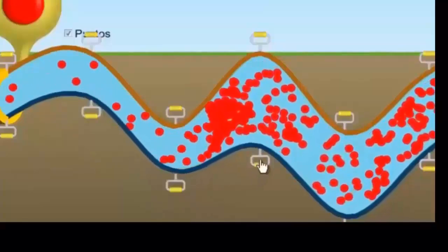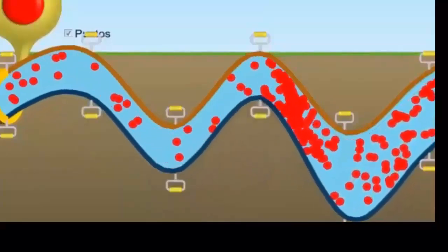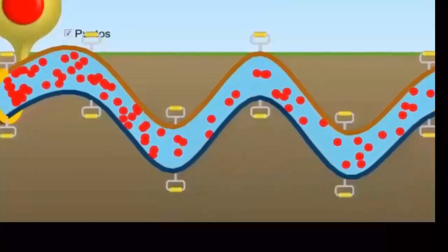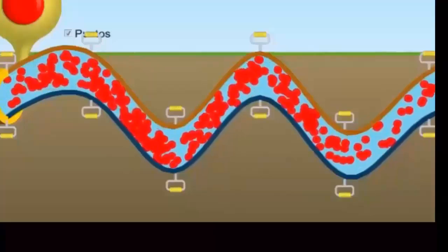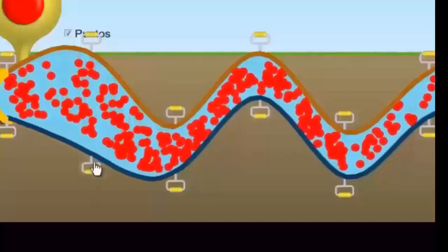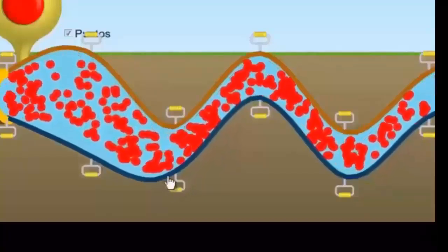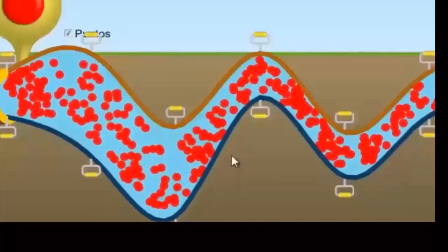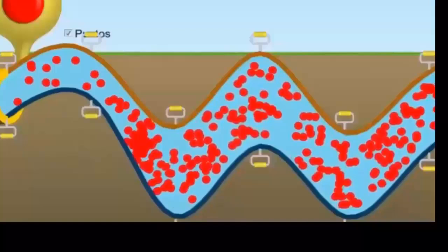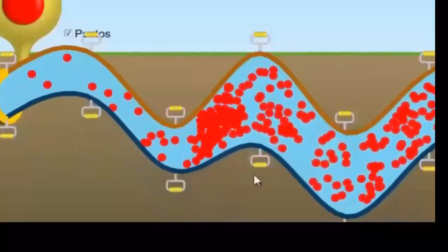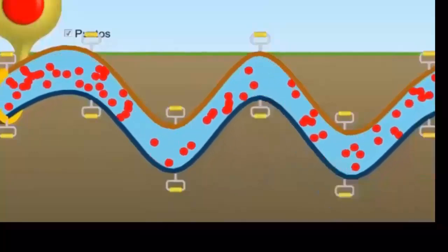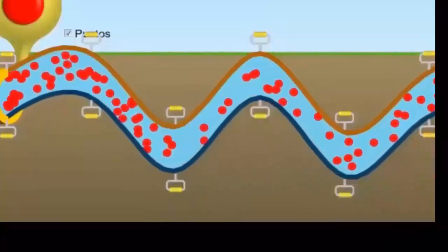E. Adjusting the capillary length is a better method for calibrating its final restriction. F. However, using excessively long lengths to increase restriction is not only inefficient, but also ineffective in many cases. In such cases, change the diameter instead. G. Conversely, excessively short lengths cause small changes to result in significant variations in flow, leading to operational problems.